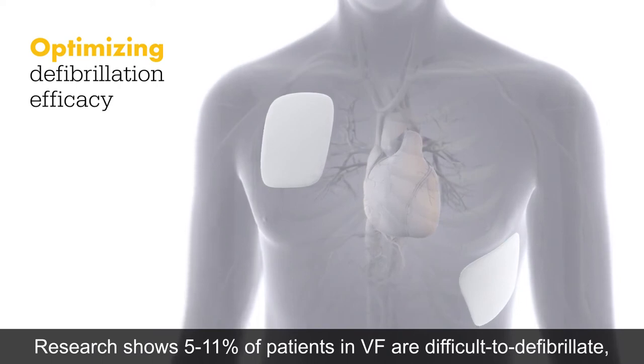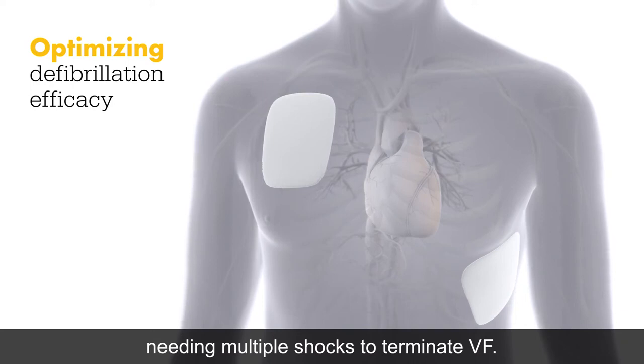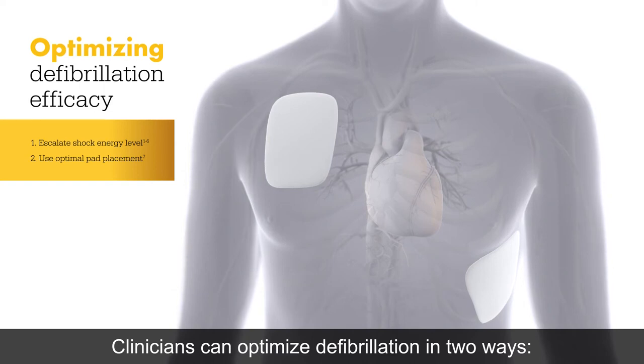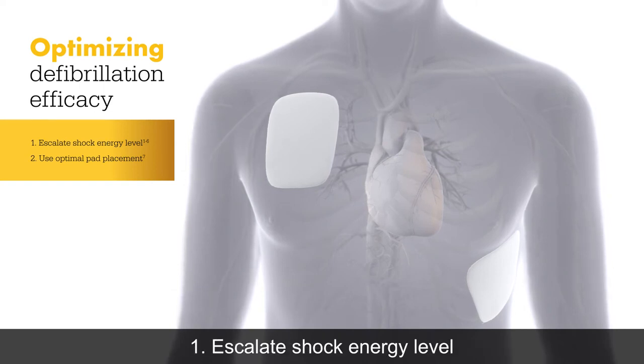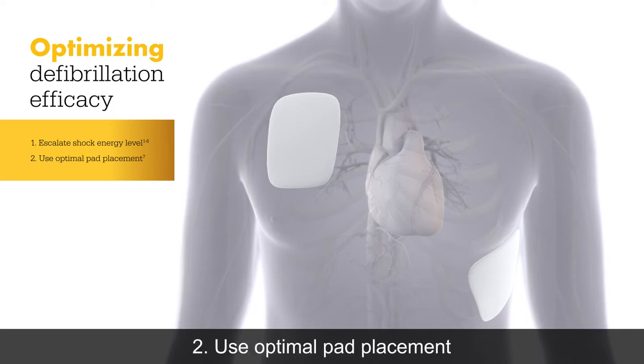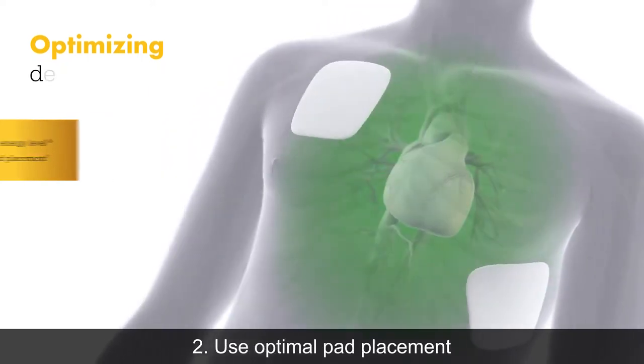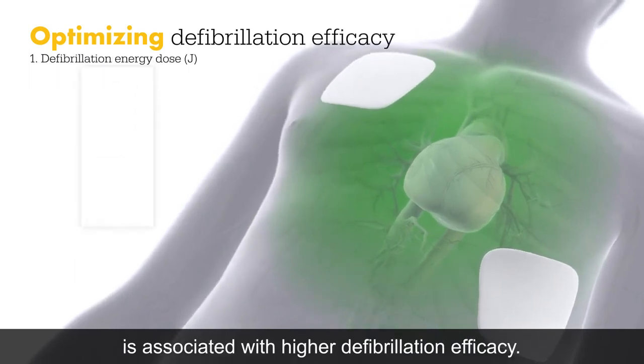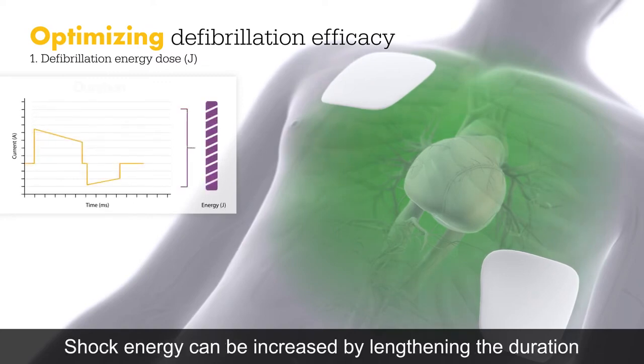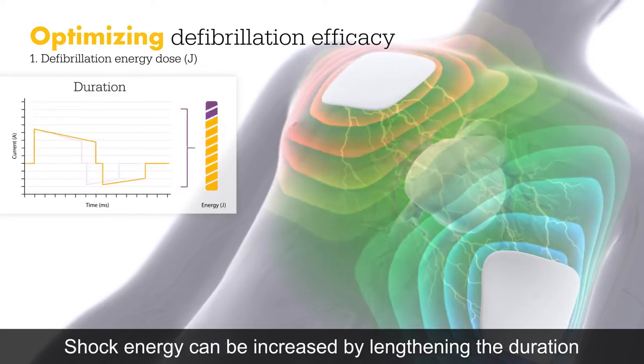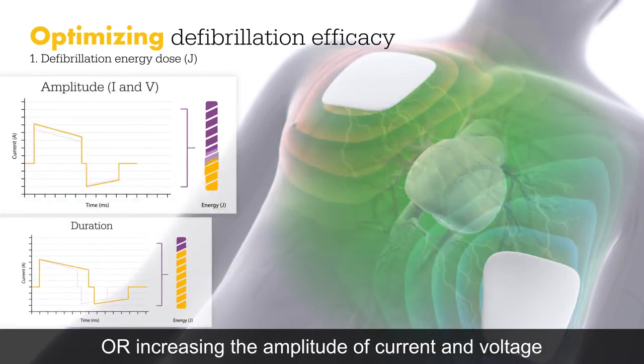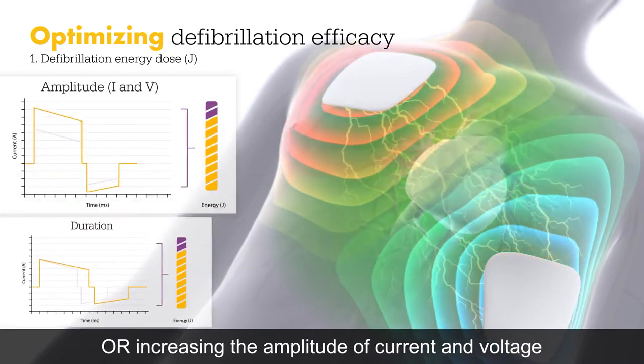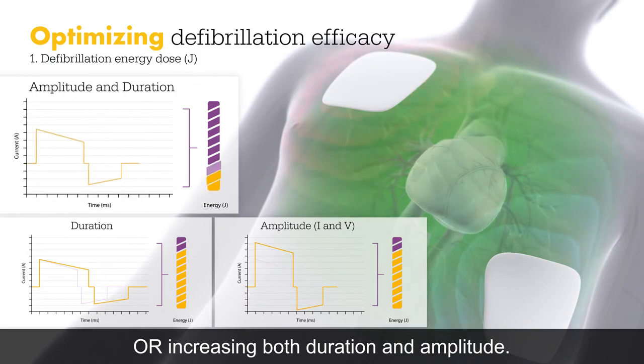Research shows 5 to 11 percent of patients in VF are difficult to defibrillate, needing multiple shocks to terminate VF. Clinicians can optimize defibrillation in two ways: first, escalate shock energy level; second, use optimal pad placement. Higher defibrillation energy, or shock dose, is associated with higher defibrillation efficacy. Shock energy can be increased by lengthening the duration, increasing the amplitude of current and voltage, or increasing both duration and amplitude.